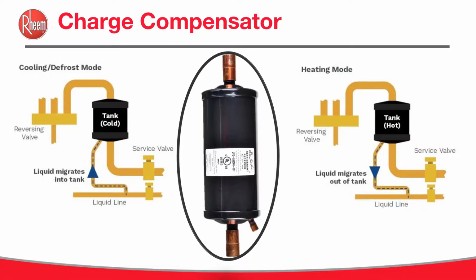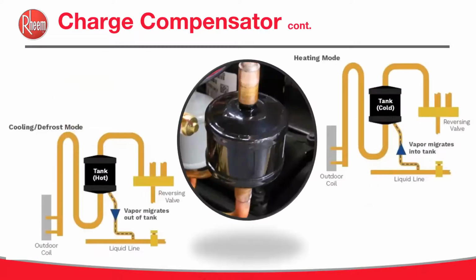So this is engineering due to sizing of coils. This doesn't mean you can mismatch systems. This is just an engineered system way of doing it. But we're not done there yet. They're not always located between the reversing valve and the indoor coil. We can also locate them between the outdoor coil and the reversing valve.